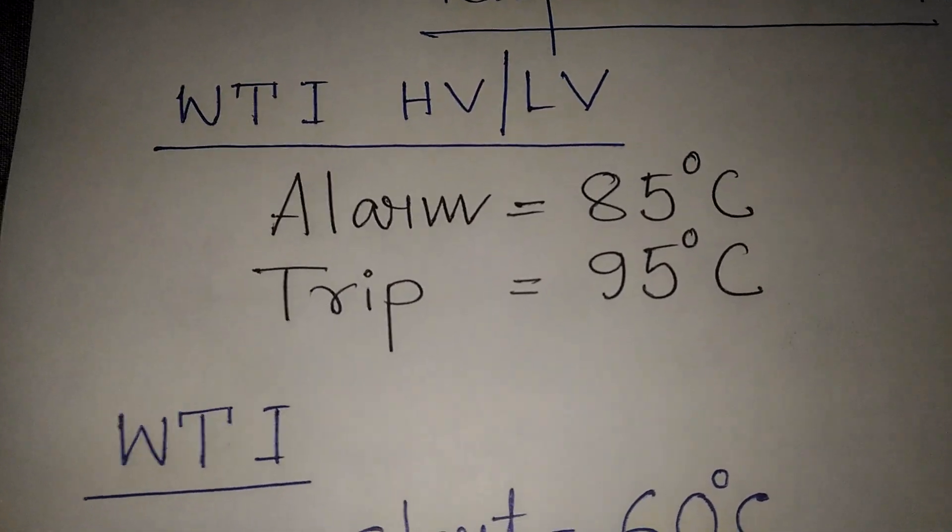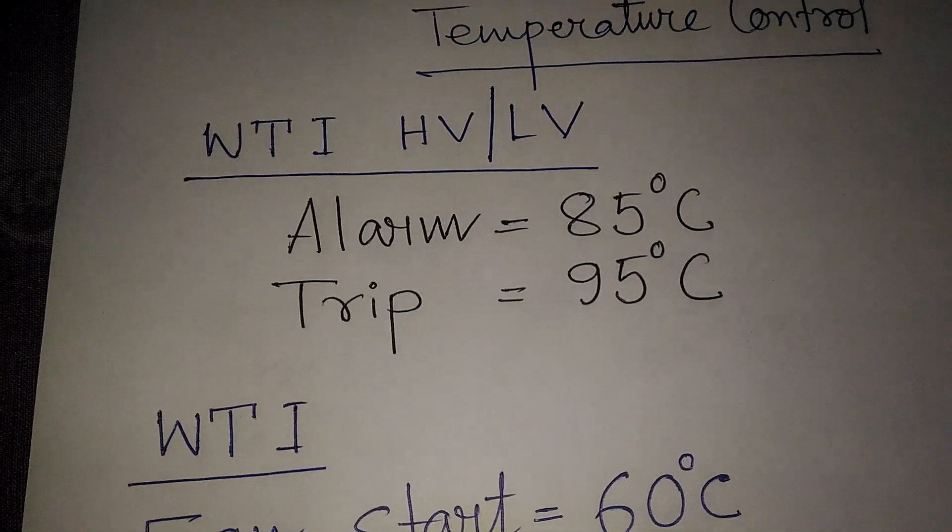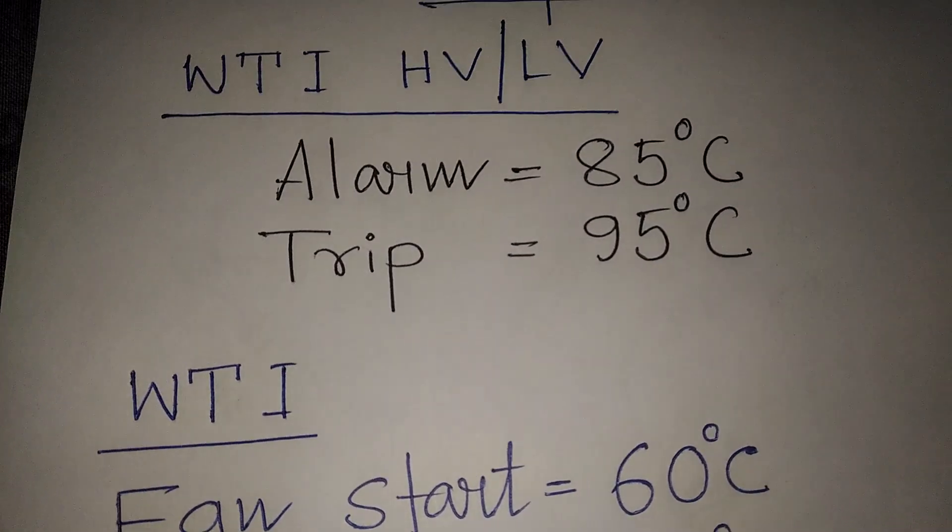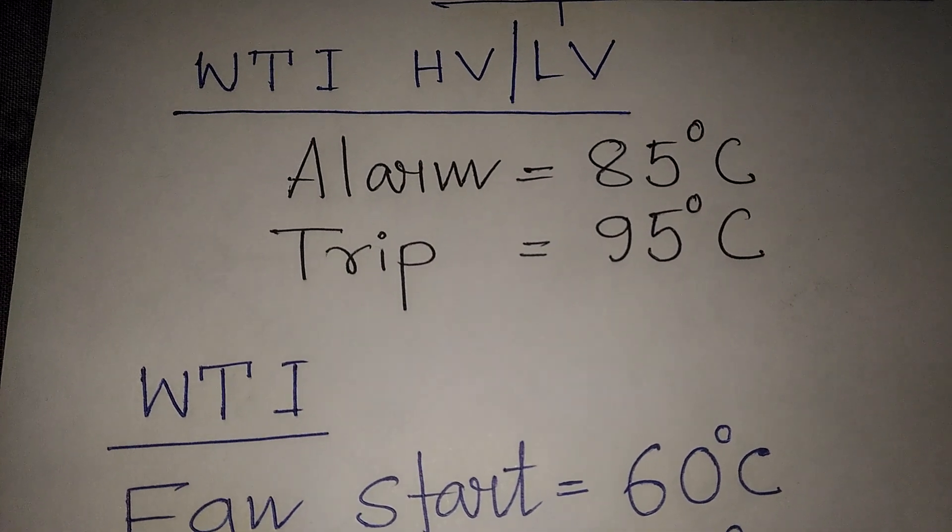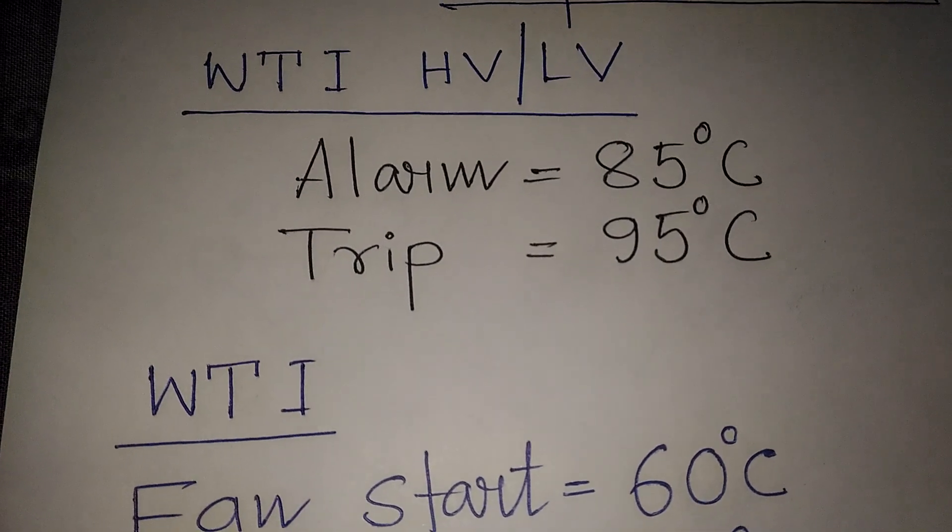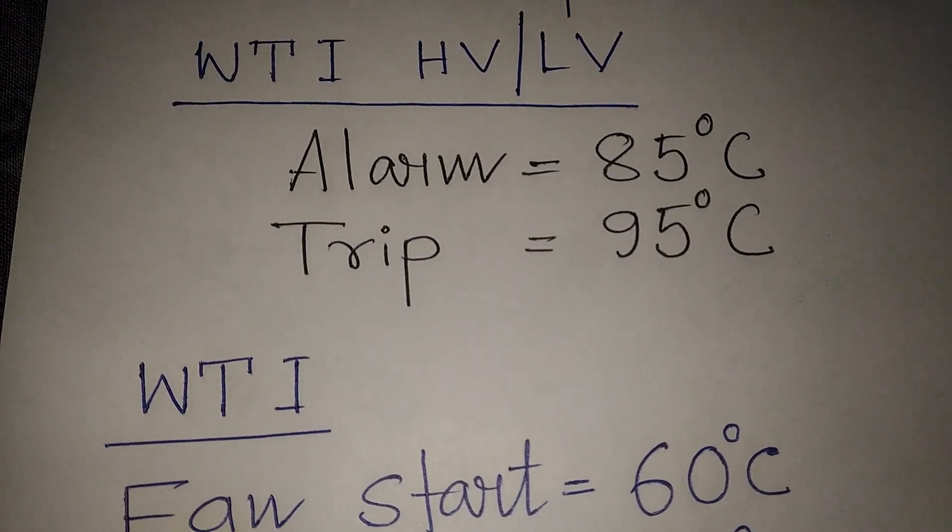In case of the WTI, we can set the alarm. The WTI alarm is 85 degree centigrade and trip of the transformers is 95 degree centigrade.